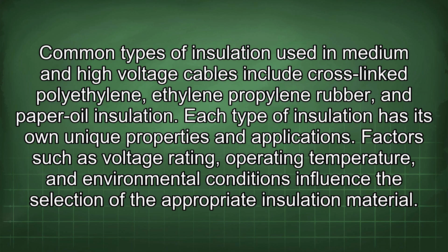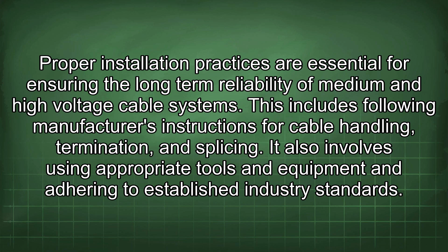Proper installation practices are essential for ensuring the long-term reliability of medium and high voltage cable systems. This includes following manufacturer's instructions for cable handling, termination, and splicing. It also involves using appropriate tools and equipment and adhering to established industry standards. Cable terminations and splices are particularly critical points in the system, as they are often the weakest links. Improperly made terminations or splices can lead to insulation breakdown, overheating, and ultimately failure.